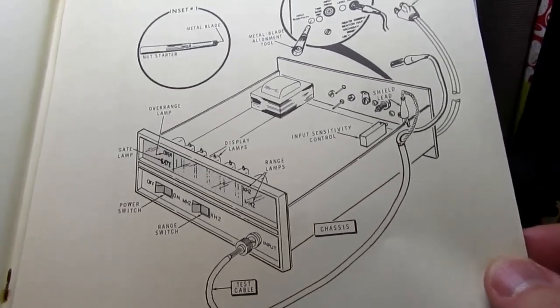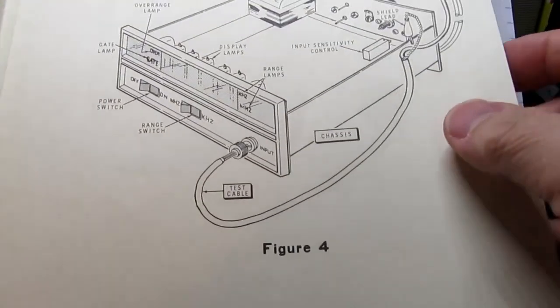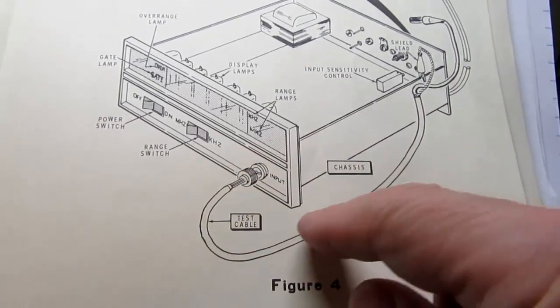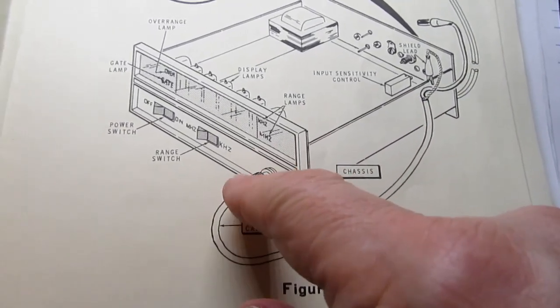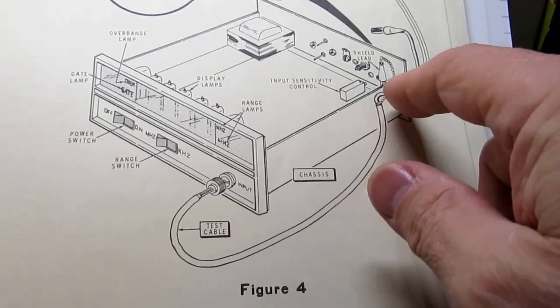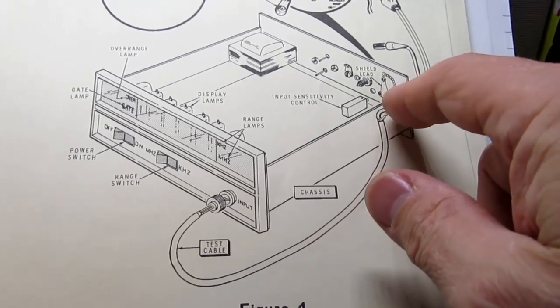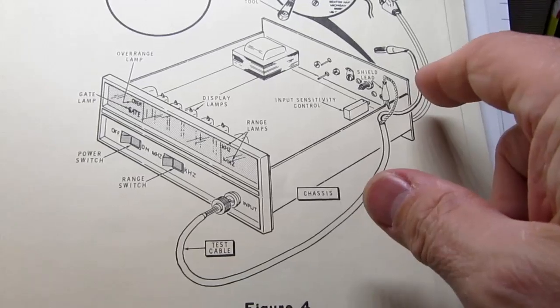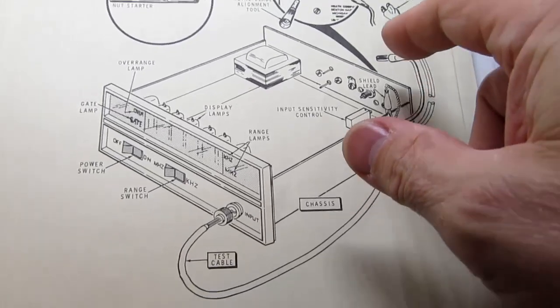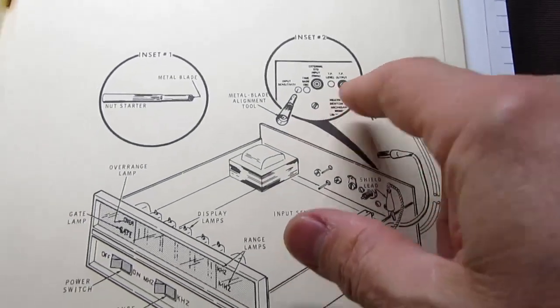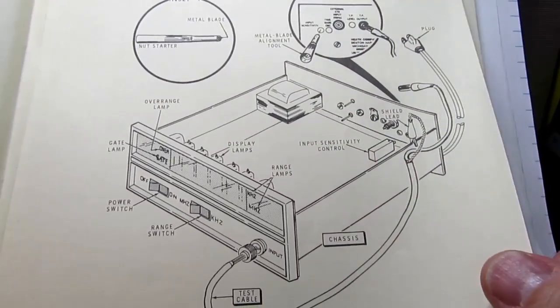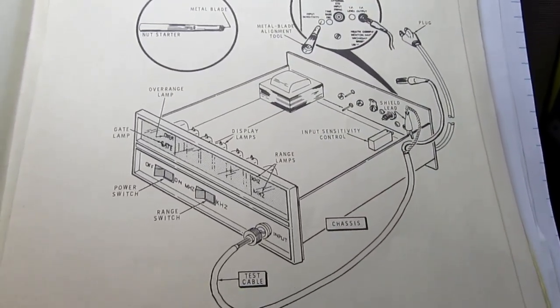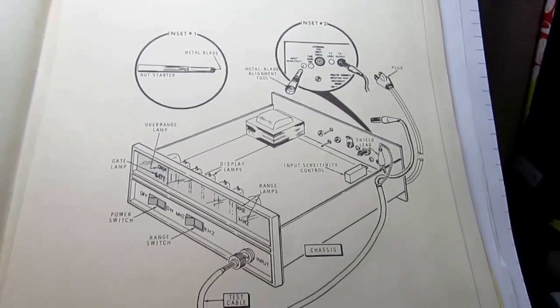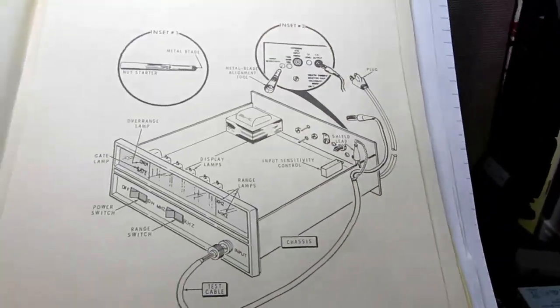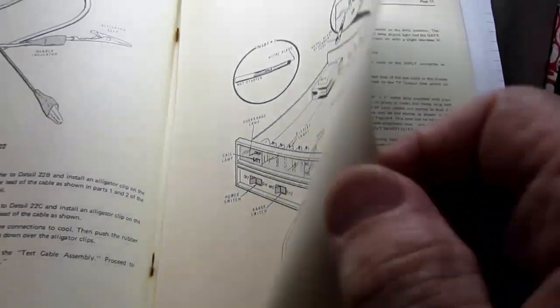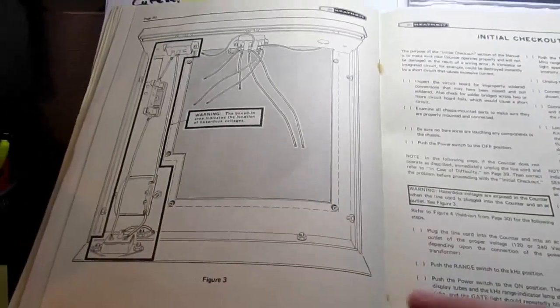And this is talking about the self-calibration, that you use the cable you've made, plug it into the front input, clip the negative alligator clip to the chassis, and the positive one to the test point, which produces a 1 megahertz frequency ideally. And I'm sure they have some iterative process for self-calibration that way.